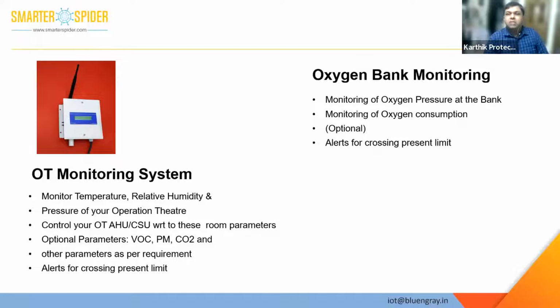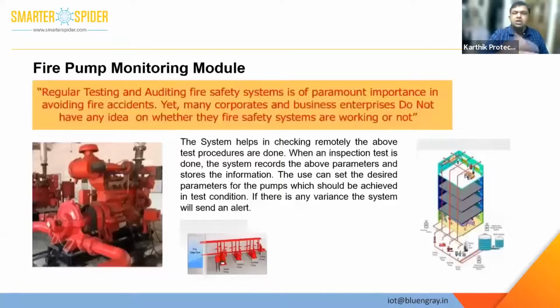Then you have an oxygen bank monitoring system where we can monitor the oxygen pressure. We can also monitor the oxygen consumption, and we have alerts for crossing the preset limit. Now, the second point which I want to highlight is the fire pump monitoring module.